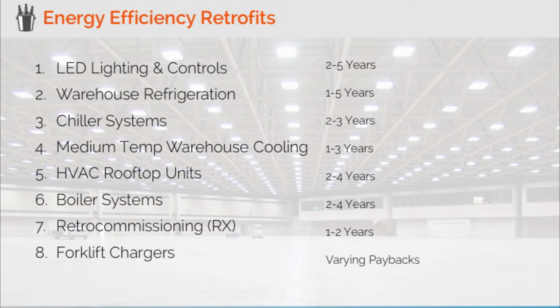Variable speed EC motors are twice as efficient as a split capacitor motor or a three-phase motor, and controllers read the flow of refrigerant and place the fan motors on a high or low speed if the compressor is on or off. It's typically half the time. So this is a major savings. The condenser fan motors can also be replaced with variable speed EC motors and can be staged so that a group of motors turn on, all in varying ways that allows for minimum energy consumption.